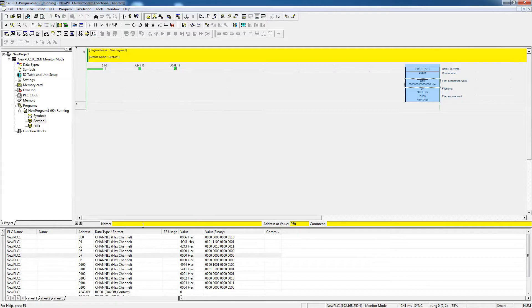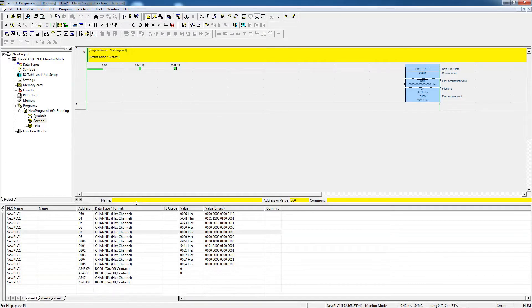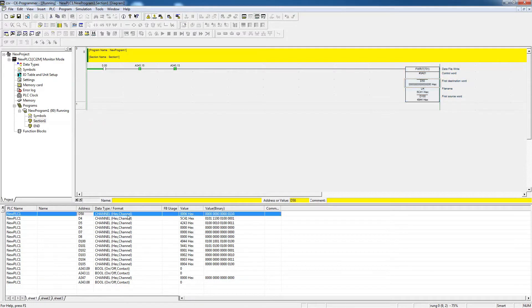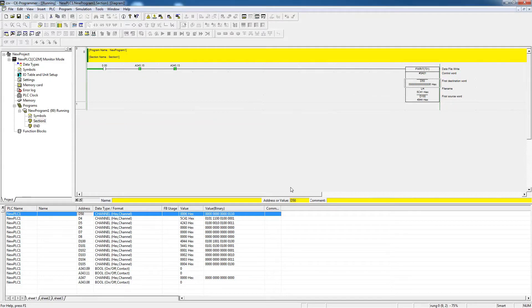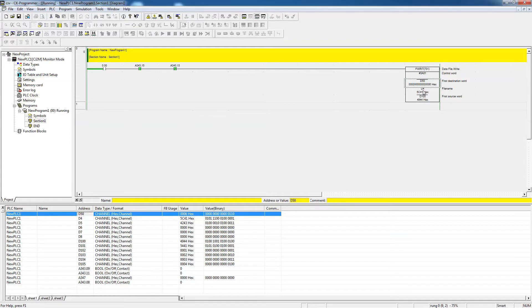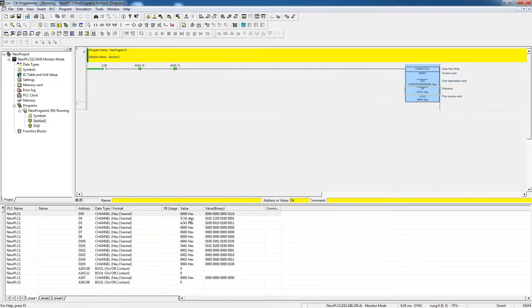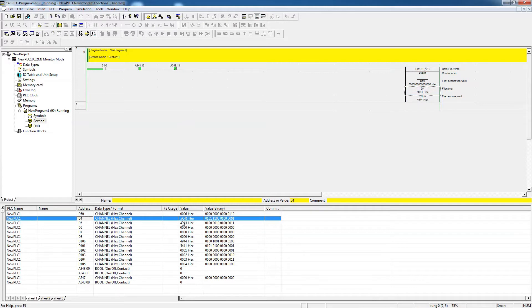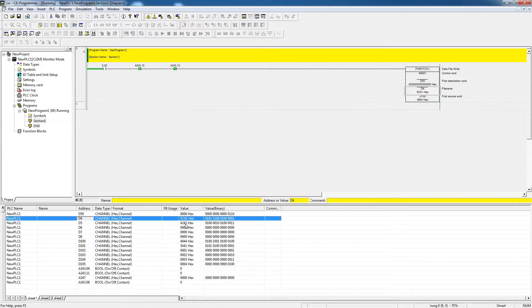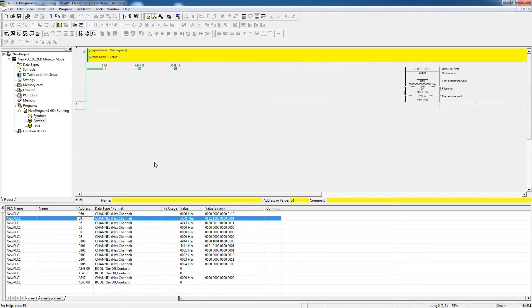And then for the T, the first destination. In here, we have basically the D50, and I want to store six words. So that's why I specified six words. And then the other words, they are all zeros. And you will see once you go to the help file, when you're storing for CSV, you just leave those as zeros. And then the file name starts from D4. Now you will see here, I have 5C, which is just the backslash. 41 is A, and then 42 is B, and 43 is C in hex. So if you convert those to ASCII, that's what you're going to get. And that's what we're going to see when we look at the EM area. We're going to see that the file that was created has a name of abc.csv.